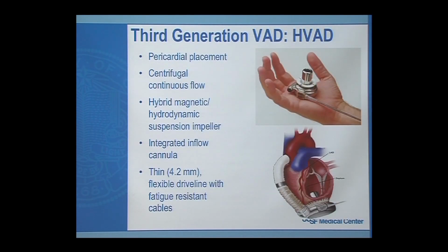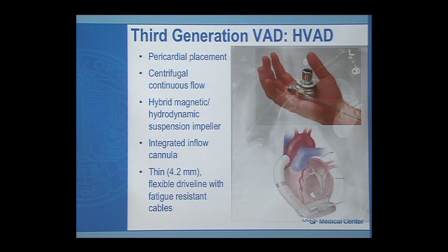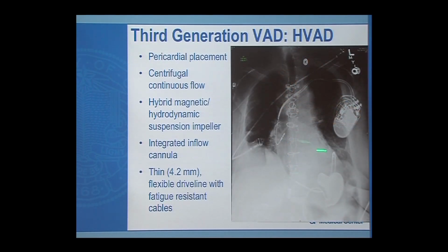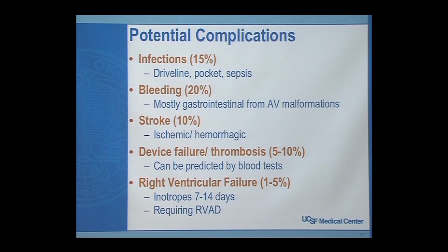And finally, this is our jewel of the day, the third generation pumps. This is really how small they are. They get implanted into the heart directly, and then you have a connector that goes into the big blood vessel of the heart. And if you look at the X-ray, the size is the same as a defibrillator. So really very, very small pumps. Very good durability, probably over 10 years, at least on the bench testing. They have 10 years of life.